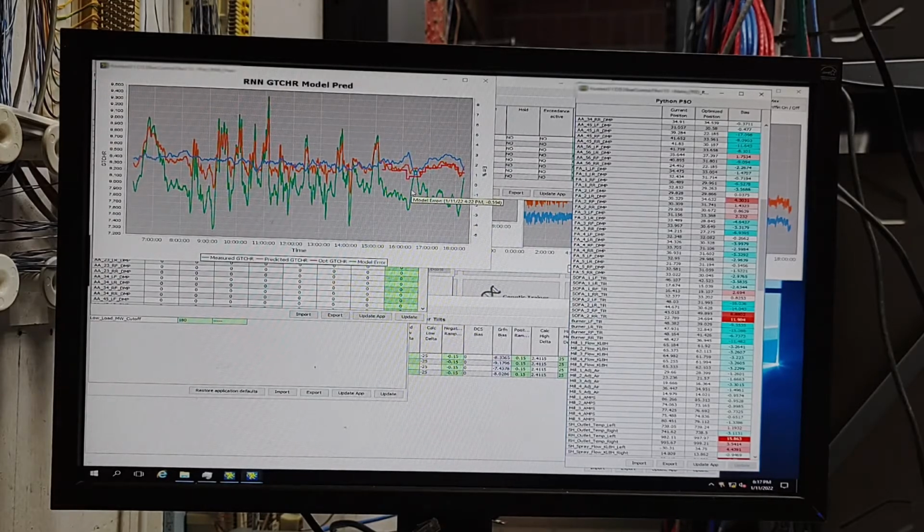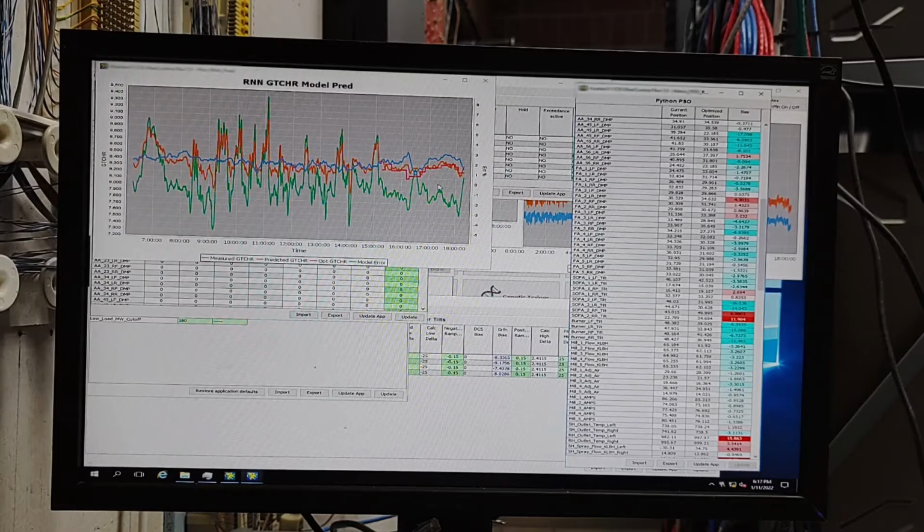to start getting a good representation of the unit, and then over the last hour the heat rate on the unit decreased by about 2.5 to 3%. This is really good performance. Typically we observe heat rate improvements in the 1 to 1.5% range.